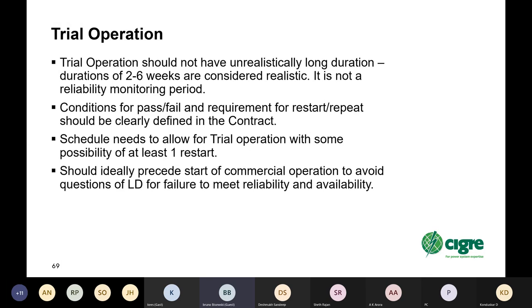Conditions for pass or fail, and the requirement for restart and repeat, should be clearly identified in the contract. The schedule needs to allow for trial operation and also some possibility of at least one restart. So you can't set the COD very tightly or allow the margin of the schedule to get so small that you can't do a restart of the trial operation. And it should typically precede the start of commercial operation to avoid questions of liquidated damages for failure to meet reliability and availability.